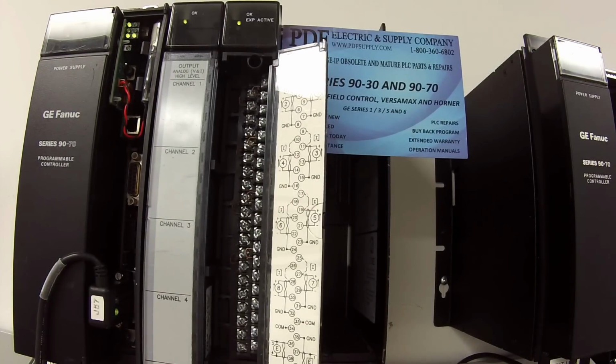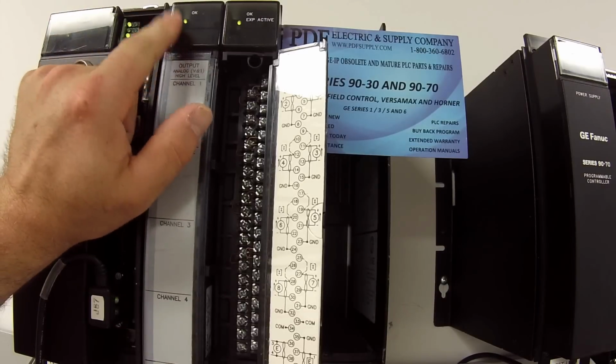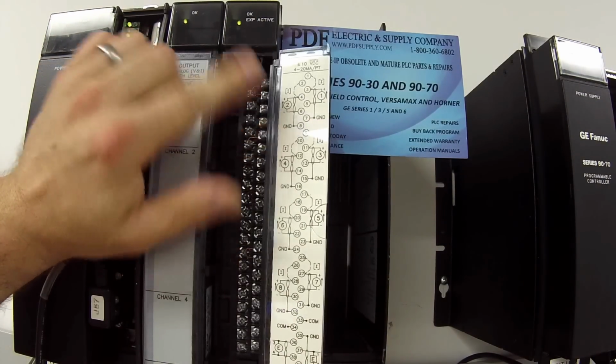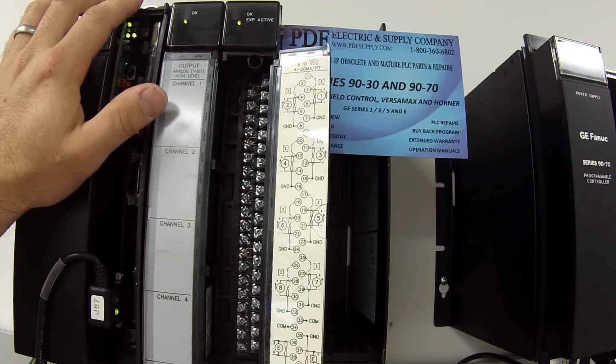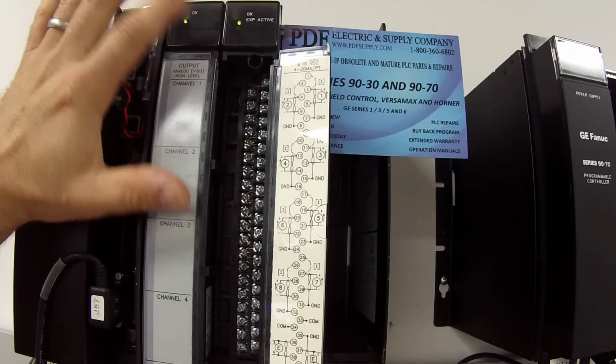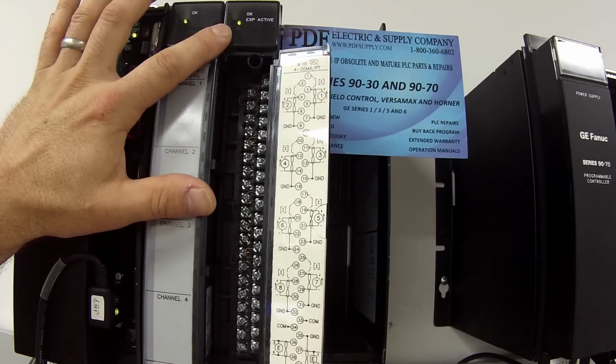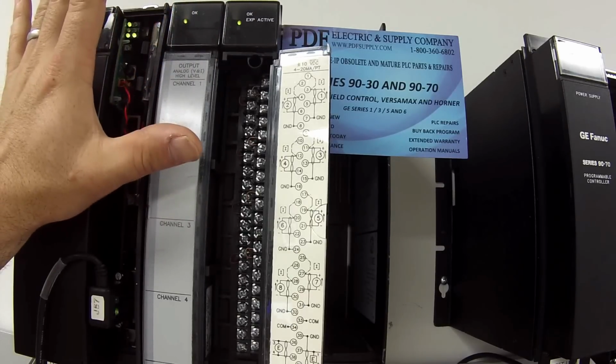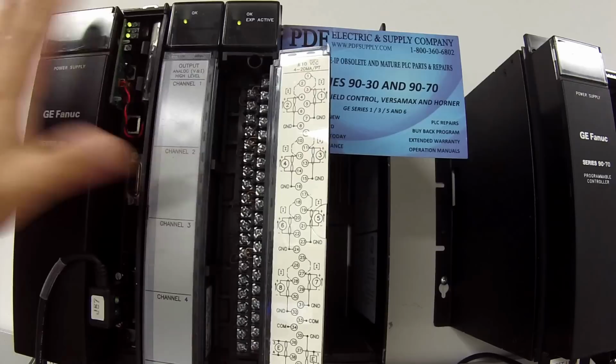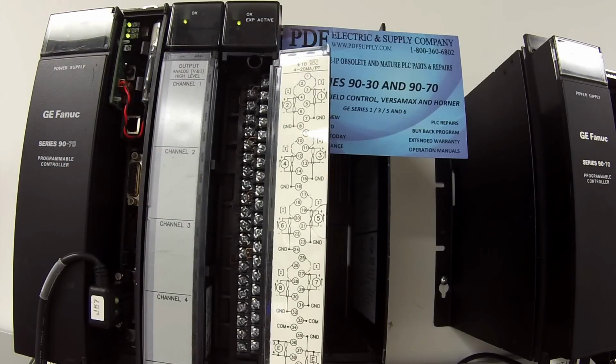As I've stated before on the ALG230, occasionally the OK light may be off when you first power it up, but then it comes on when the CPU is configured properly, or maybe it's on the whole time for you. But it's not always a solid indicator; if it doesn't come on immediately, it doesn't always mean that there's something wrong with it right off the bat. But if you go through this test and you go through all these readings and your readings are not consistent, and the Proficy software is configured so that it should all be the same, then there's definitely a problem with it. And then, of course, if you never get an OK light on, there's probably also a problem.